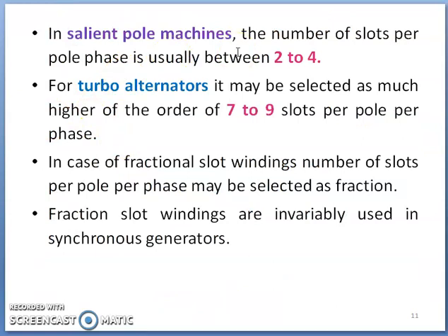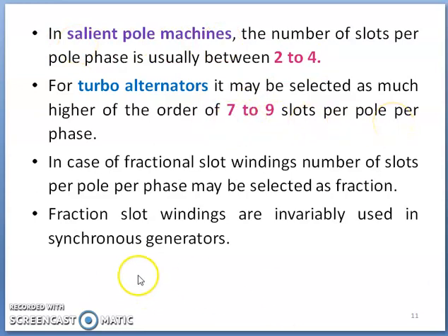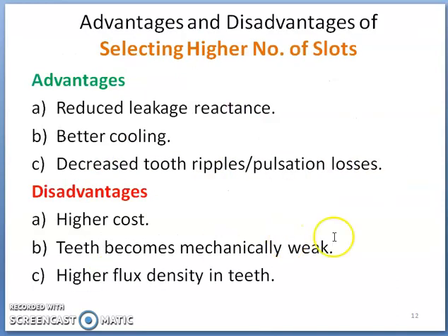For salient pole machines, the number of slots per pole per phase is usually between 2 to 4. For turbo-alternators, the number of slots per pole per phase is more — typically 7 to 9. Sometimes, fractional slot windings are also used in synchronous generators, in which case the number of slots per pole per phase may be selected as a fractional number.